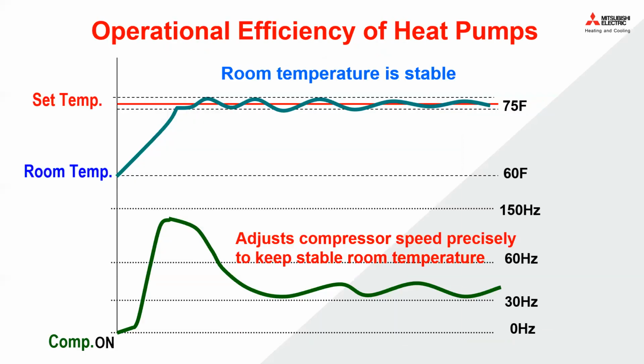So unlike conventional systems, which cycle on and off, a heat pump system will detect the changes in the room. So you have thermistors, obviously you have the thermostat, you have them on the intake, you have them on the outdoor unit. So it's constantly checking what the temperatures are in its surroundings. And so then it's going to ramp up the compressor to hit your set point, and then it's going to slow it down so it can maintain that. So it's not like our traditional system where it goes full speed, hits set point, and then turns itself off. It's actually going to go up gradually, hit a set point, and then coast. And that's where you get a lot of your energy savings.